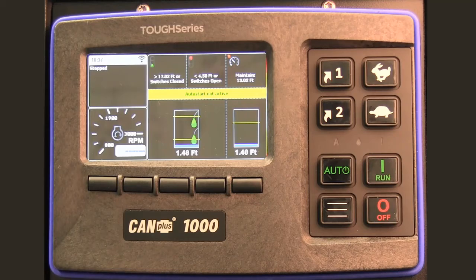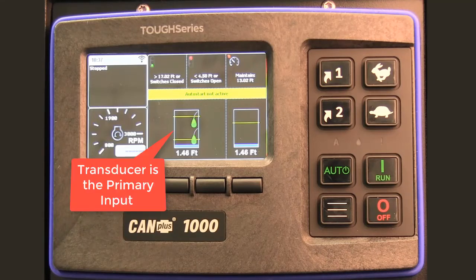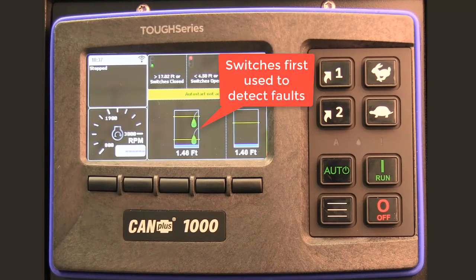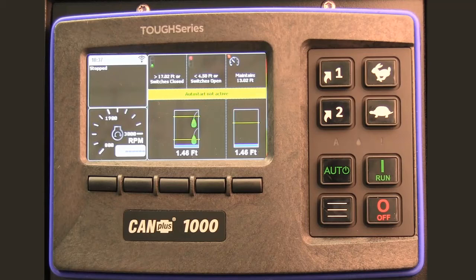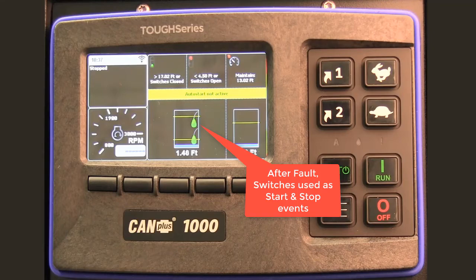At this point, it is very important to point out the relationship between the switches or floats and transducer. When configured and equipped with transducer with backup switches, the panel will use the transducer to determine the primary start and stop events. The switches are used to detect transducer faults, and when a fault is detected, the panel will automatically adjust to use the switches to detect the start and stop events.